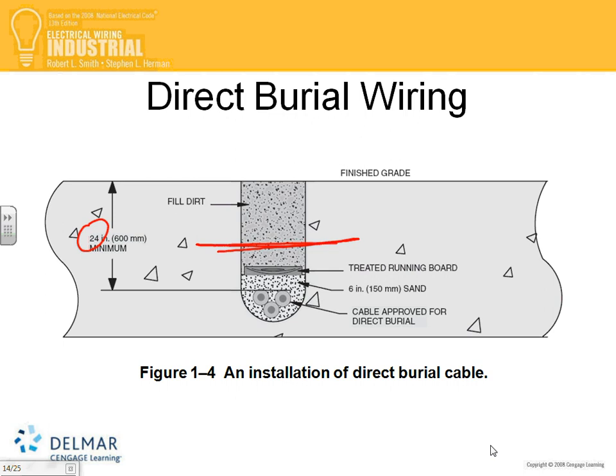Yeah, you can put electrical warning tape right above it. The only location by code you need a warning tape right now is if it's a service. Is it a good idea if you bury a cable to have a warning tape that says electrical power, be careful? It's a good idea, but by code it's only required on a service.